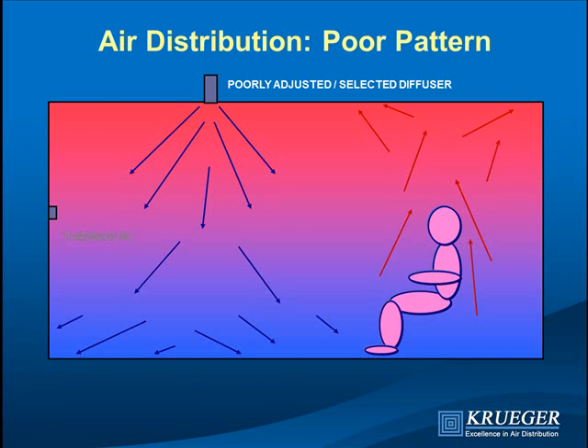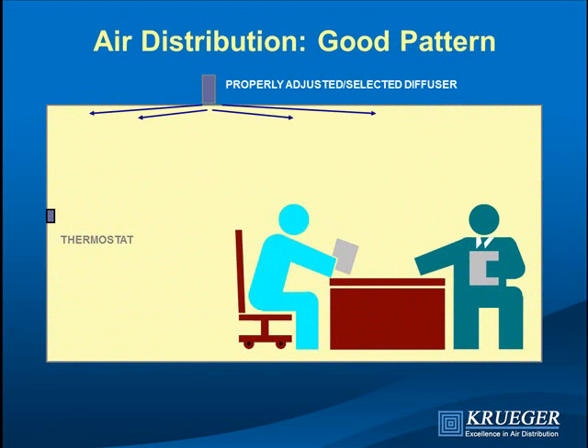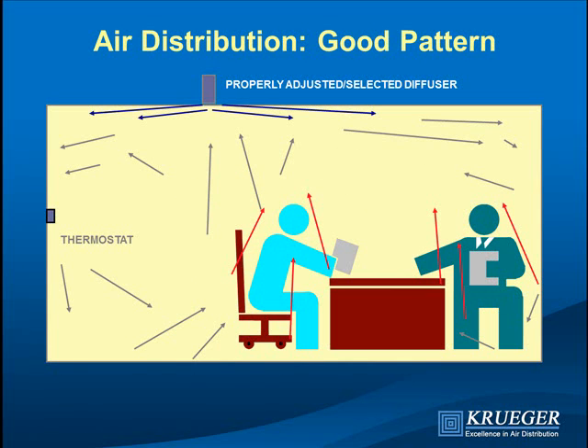What we want is for the diffuser to provide a horizontal pattern. In a nine-foot ceiling, a linear diffuser should almost always be set to blow horizontal, even near windows. The goal is to get heat rising from people and equipment well mixed so the thermostat can sense what's happening, resulting in uniform temperature in the occupied zone.